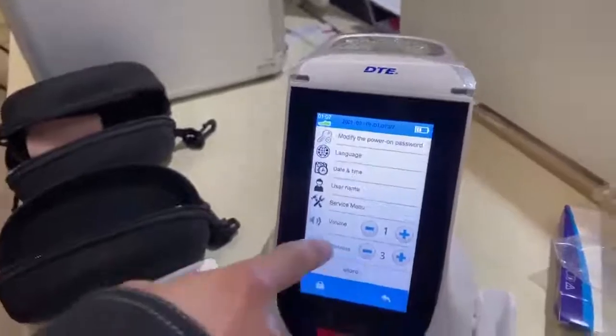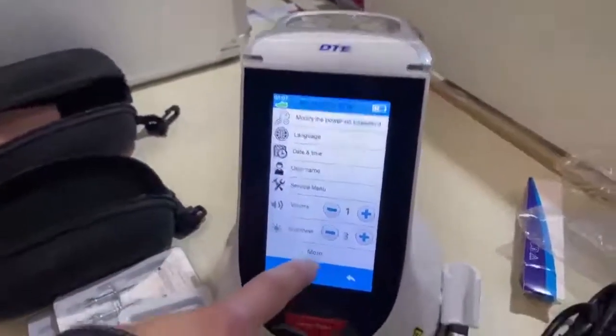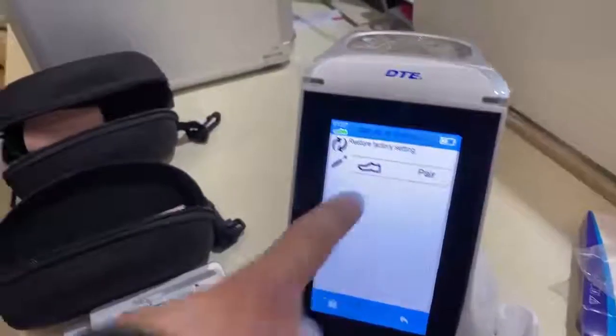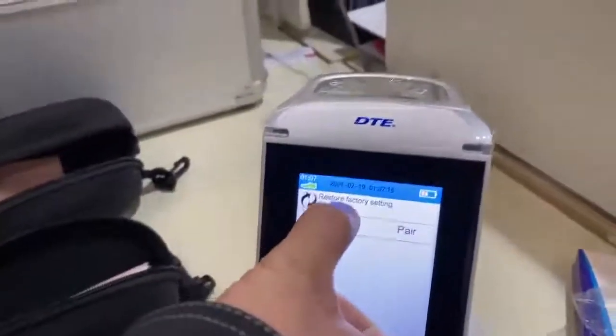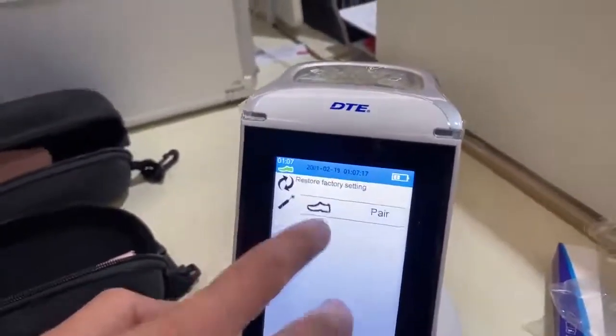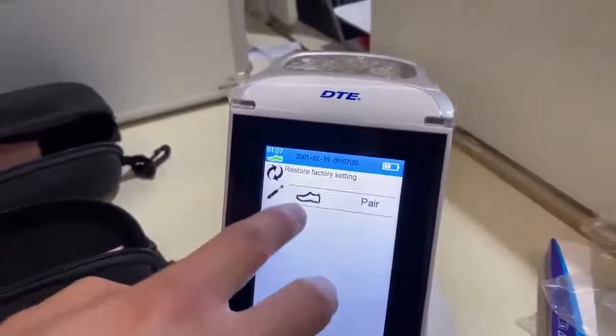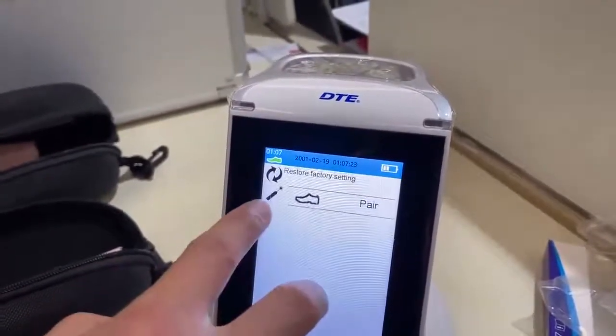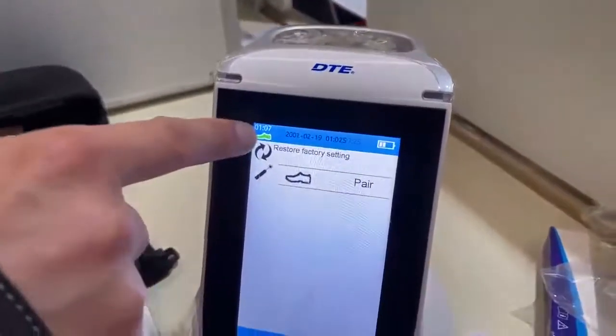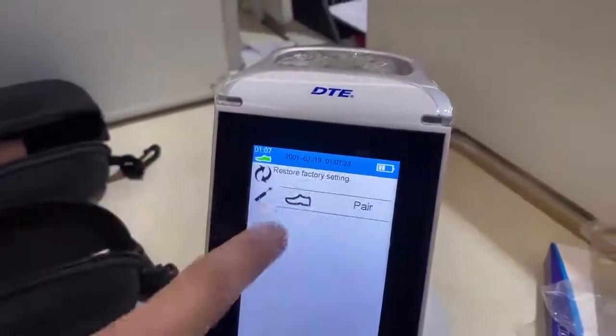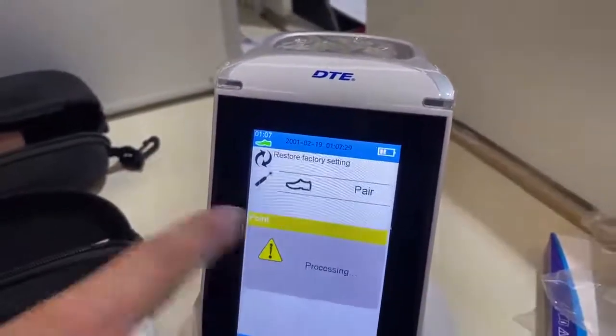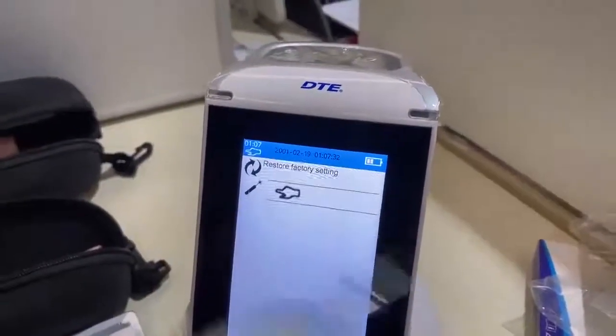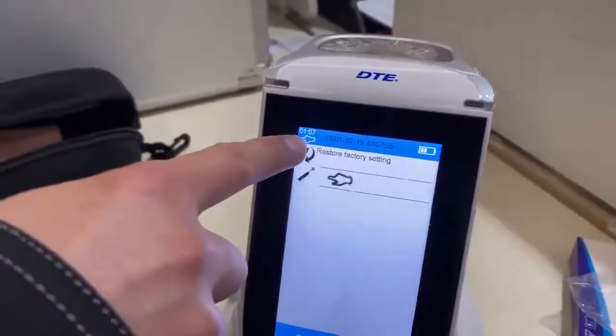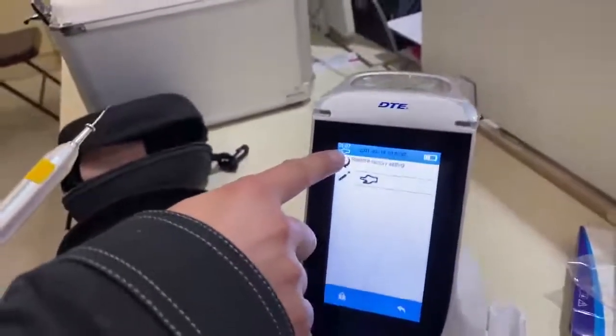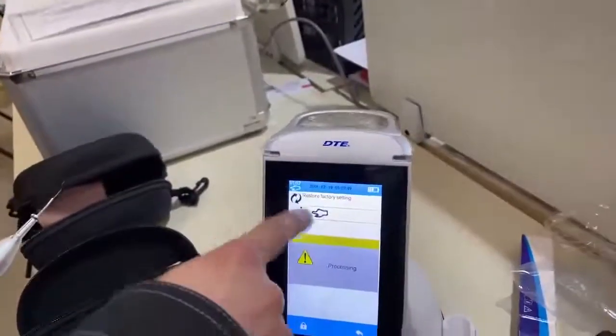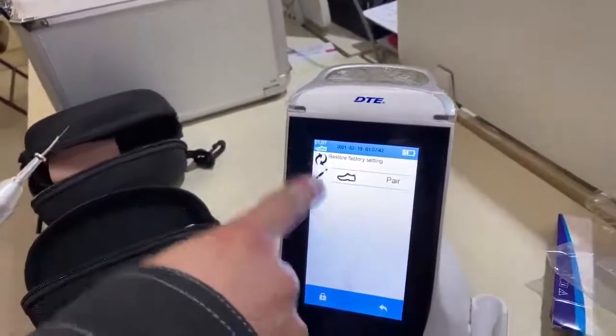And also the volume and brightness. And here is the more button. If you press the more button, you can see there is restore the factory setting. And you can see this is for foot control, this is for hand control, and now it is the foot control, right? And how can we change? We just press this button. Now it will change to hand piece control. You can see the mark will change to a hand. So we press here, we can change between foot control and hand control.